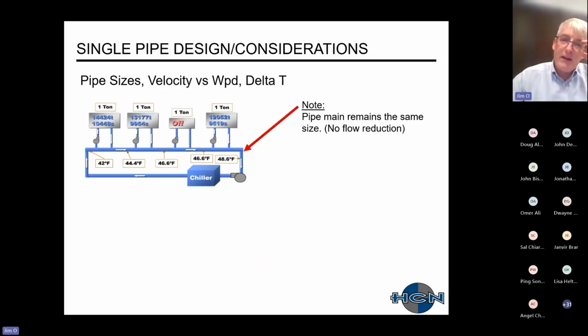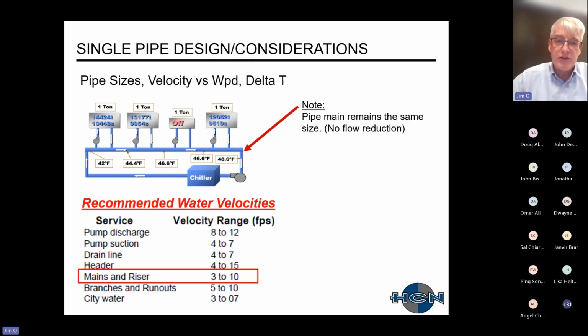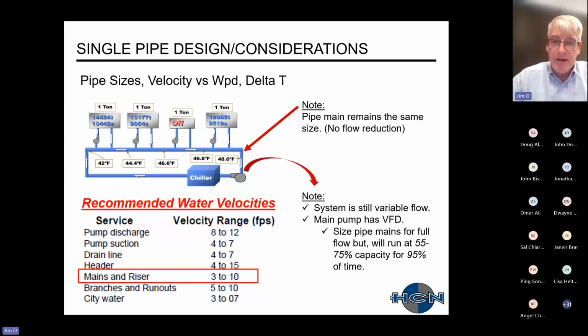So first, let's talk about the pipe sizes. Pipe sizes have to do with velocity versus water pressure drop, also the delta T. I want to point out once again that the piping main will remain the same size throughout, because we don't have any flow reduction. And then once again, from ASHRAE or old rules of thumb, etc., your water velocities and pipe sizes still follow the old traditional rules for your runouts and pipes and mains. All right. And once again, as I mentioned before, your main circulating pump still has a VFD.